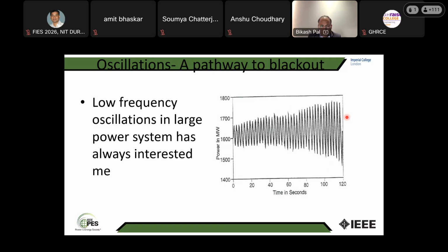And this oscillation now has many consequences. When this oscillation happens, you have the power swing blocking relay that would pick up that oscillation. That is essentially a distance relay zone 3 element, which will be looking at the oscillation. If the oscillations are stable, it would move across the impedance plane very slowly, and it will be detected as a stable oscillation. So the power swing blocking relay will always send a signal that it is a stable swing. But if the oscillations are unstable, then the relay will disconnect the line. And once the line is disconnected, then you don't have power flow.